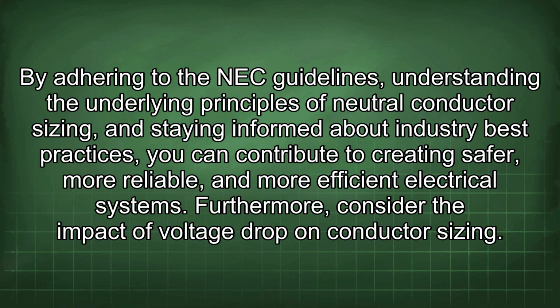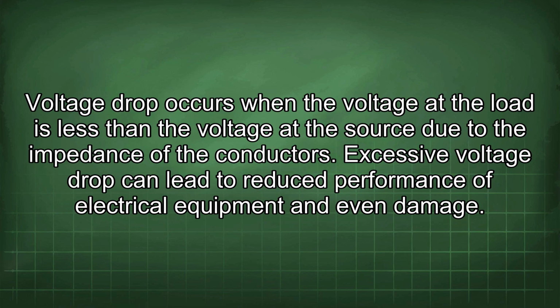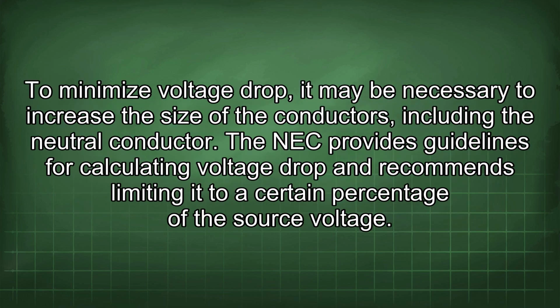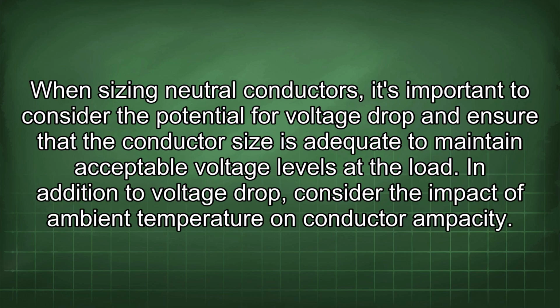Furthermore, consider the impact of voltage drop on conductor sizing. Voltage drop occurs when the voltage at the load is less than the voltage at the source due to the impedance of the conductor. Excessive voltage drop can lead to reduced performance of electrical equipment and even damage. To minimize voltage drop, it may be necessary to increase the size of the conductors, including the neutral conductor. The NEC provides guidelines for calculating voltage drop and recommends limiting it to a certain percentage of the source voltage. When sizing neutral conductors, it's important to consider the potential for voltage drop and ensure that the conductor size is adequate to maintain acceptable voltage levels at the load.